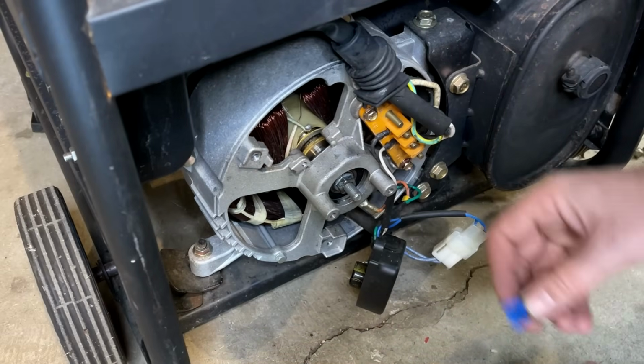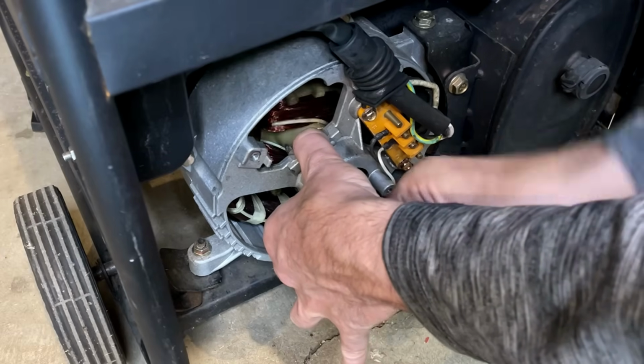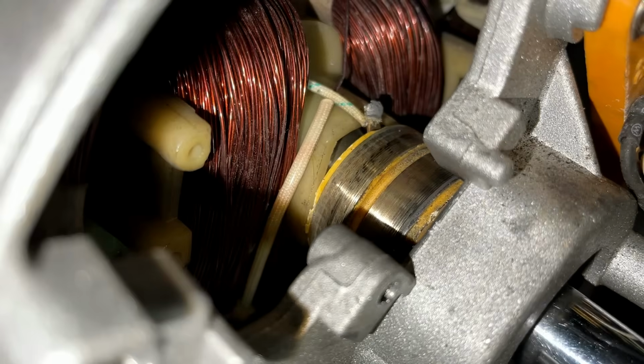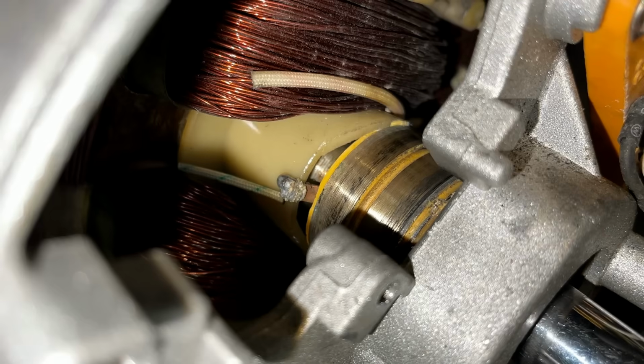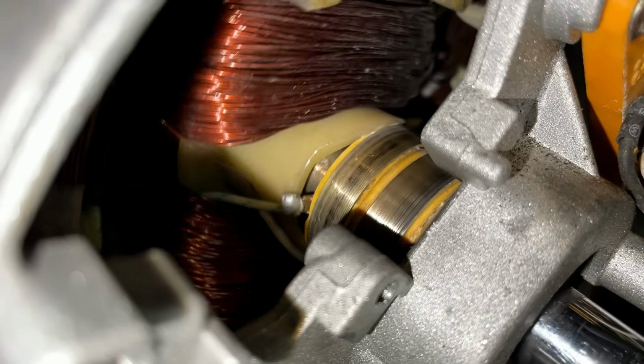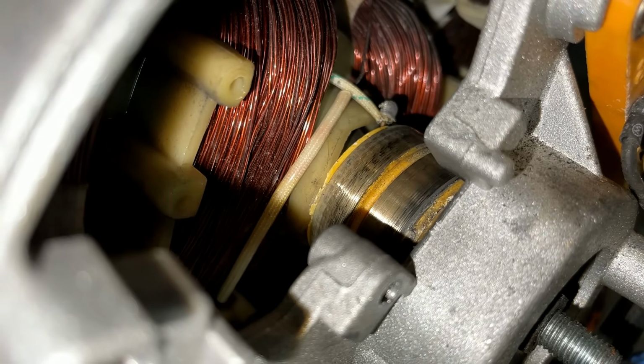They're cleaning up, but it is slow. The blue Scotch-Brite is definitely not as effective as the green. I think that's about as good as they're going to get. There's a lot of low spots, where you can still see the carbon. These slip rings, though, are pretty smooth compared to the ones on the other generator. If anything, I'd say the slip ring on the left is a bit more rough, and that one had the good brush. So let's get some new brushes on. I think we're good to go.